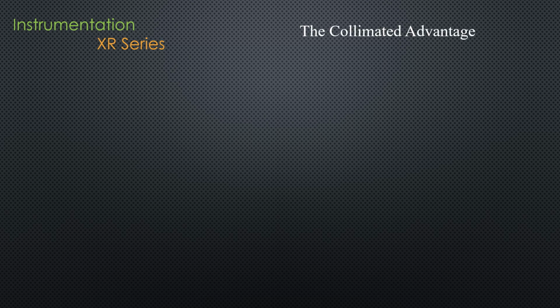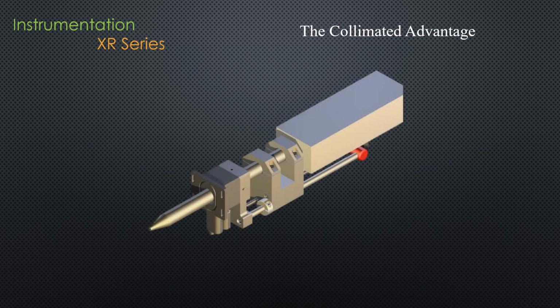Let's take a look at the XR series. This is a collimated system, and we call it a collimated advantage because it's more sensitive than a polycap in excitations above 12 to 18 kV. And it's a little more economical priced than a polycapillary system.